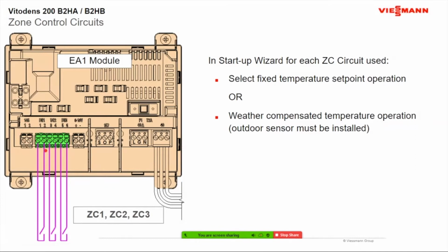So these are on the, remember that control that we're going to fold down. Say you're doing multiple zone controls, you could have 3 different multiple zone controls tied to this boiler, depending on how many BTUs the boiler is, and have multiple zones. So you could have a Taco or somebody's 7 zone control with an end switch coming over to the boiler here, and then another one tied to zone 2, and you could make one a fixed set point, and then you can make the other one outdoor weather responsive. So you can do multiple different things with this, as well as, if you're using mixing valves, you can do their own heating curves too. So you can have heating circuits as well as zone circuits with this boiler. If you don't know about heating circuits, they're more or less back in the day, like I have in my house. I have no thermostats in my house, so I do a constant circulation, and it modulates to the outdoor temperature with a room temperature set point that I do off the control of the boiler.